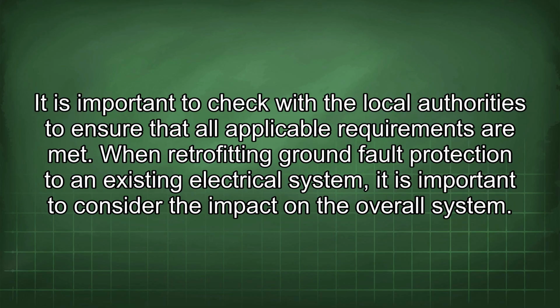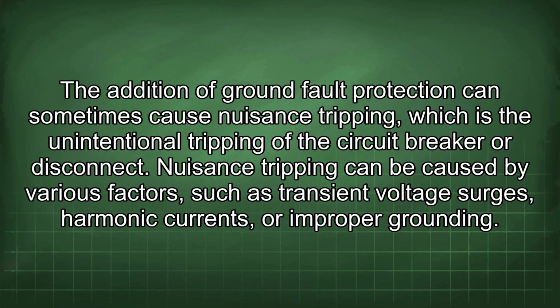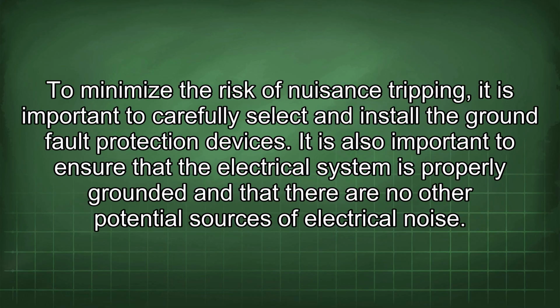When retrofitting ground fault protection to an existing electrical system, it is important to consider the impact on the overall system. The addition of ground fault protection can sometimes cause nuisance tripping, which is the unintentional tripping of the circuit breaker or disconnect. Nuisance tripping can be caused by various factors, such as transient voltage surges, harmonic currents, or improper grounding. To minimize the risk of nuisance tripping, it is important to carefully select and install the ground fault protection devices. It is also important to ensure that the electrical system is properly grounded and that there are no other potential sources of electrical noise.